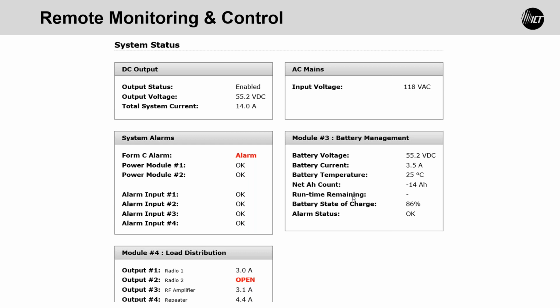battery discharge testing as often as you set it up, maybe once a month — at 2 o'clock in the morning, the system runs off the battery for an hour, and from that information it calculates the state of charge of the battery. That's where this number comes from. It also tells you, from when the system was running off the battery, what the remaining runtime was.